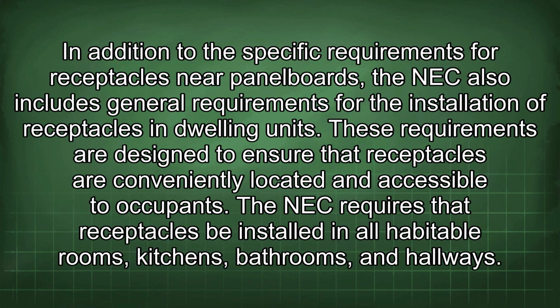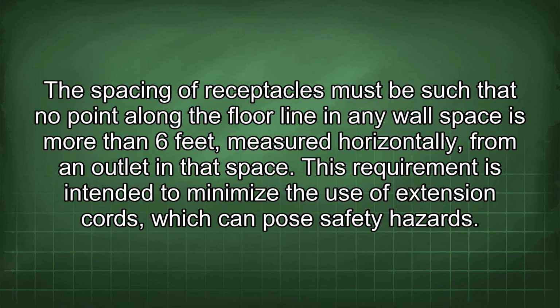In addition to the specific requirements for receptacles near panel boards, the NEC also includes general requirements for the installation of receptacles in dwelling units. These requirements are designed to ensure that receptacles are conveniently located and accessible to occupants. The NEC requires that receptacles be installed in all habitable rooms, kitchens, bathrooms, and hallways. The spacing of receptacles must be such that no point along the floor line in any wall space is more than 6 feet, measured horizontally, from an outlet in that space.